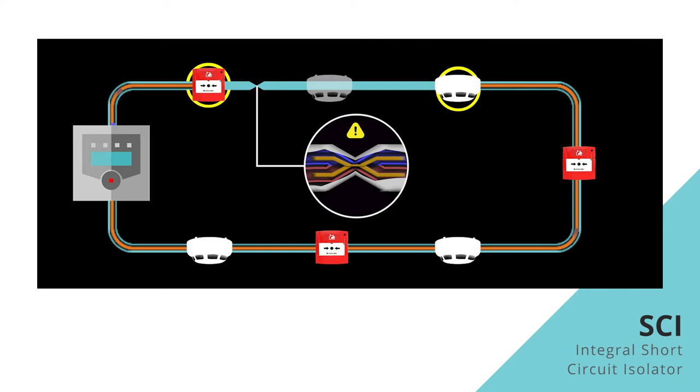As soon as they detect the drop in voltage they open, which in effect separates the two conductors again, allowing the voltage to continue to be driven. At the same time, the fire control panel recognizes it's no longer receiving a return loop drive voltage and switches to driving the voltage from both ends of the loop.